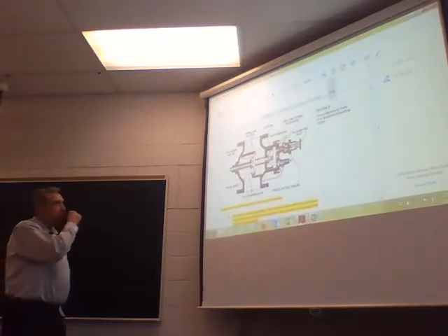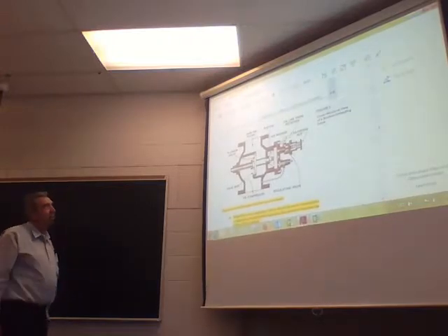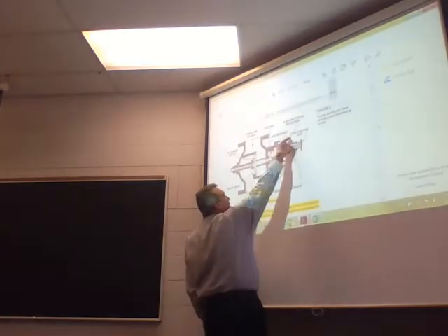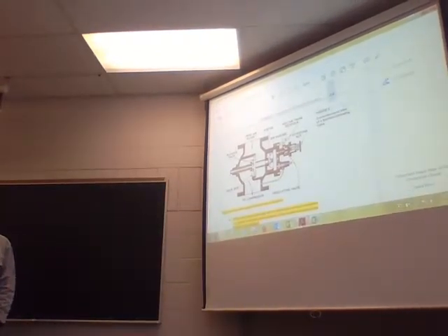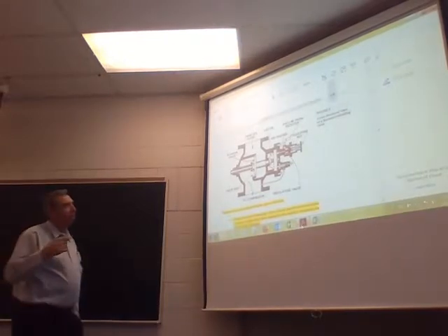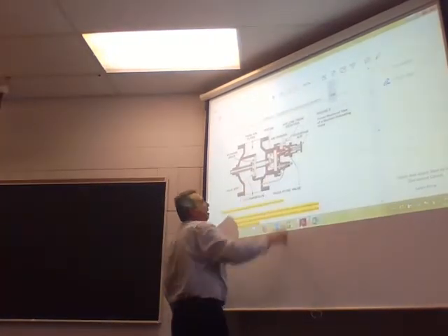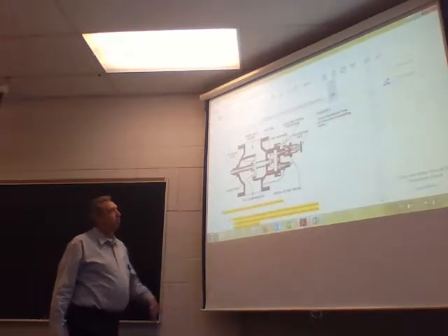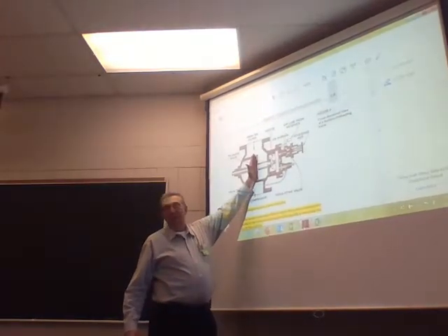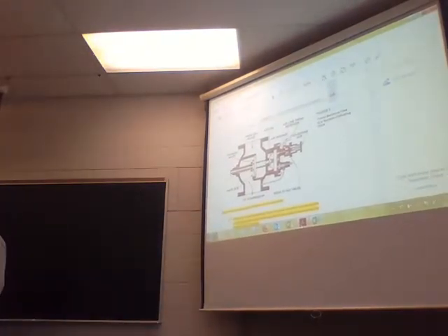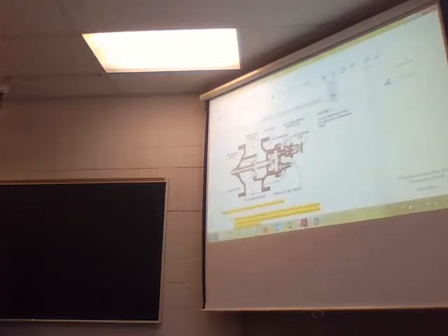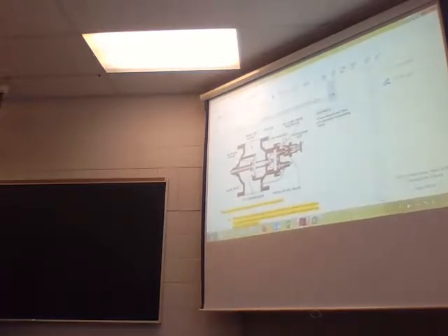So what's going to happen is when the pressure from my airline from my receiver comes in here, as soon as it reaches a predetermined pressure, 100 psi again, because I really like that number. At 100 psi, air is going to come into my air passage, and all of a sudden it's going to push this closed, wham, and now there's going to be no air getting to my inlet valve of my compressor. So again, the compressor is going to be going back and forth, round and round, and no air is going to get in, because we shut the valve off to the inlet of the compressor.